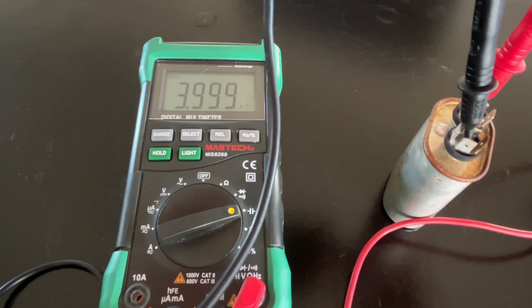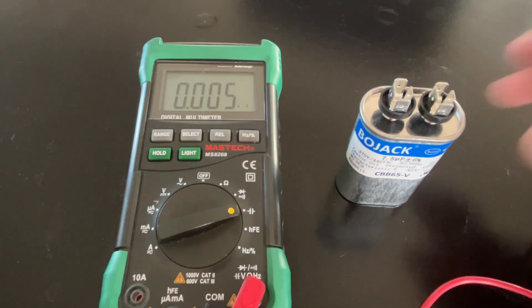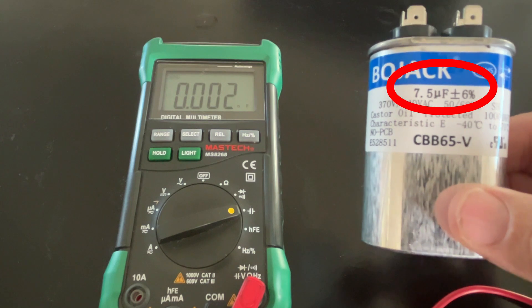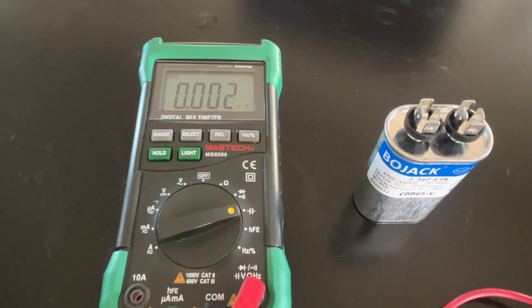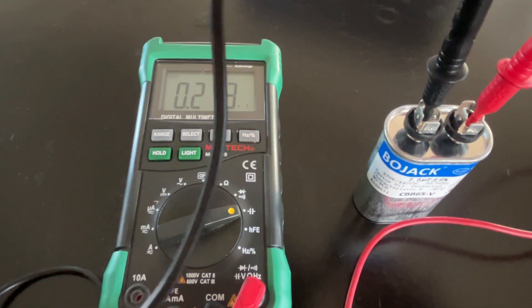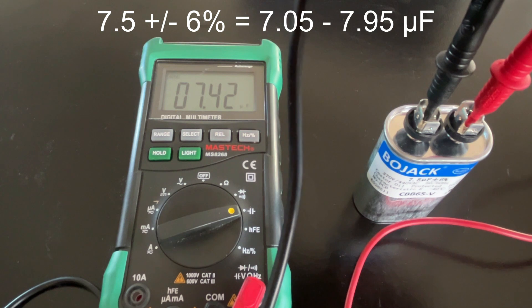All right, let's try this new one. This is a seven and a half plus or minus six percent. And we get 7.42—that's within six percent of seven and a half, so this one is good.